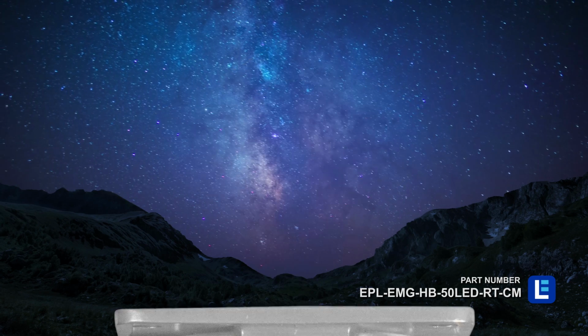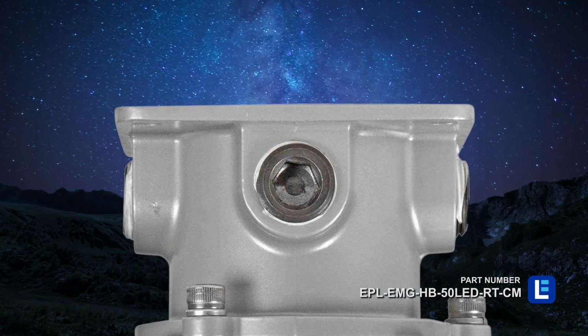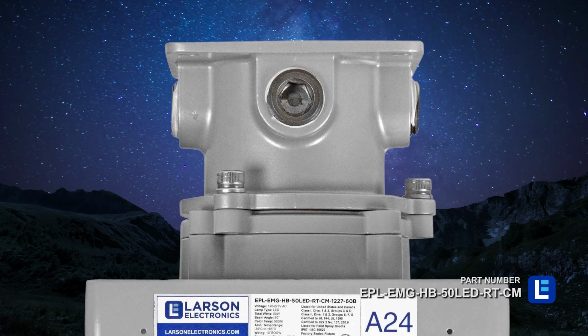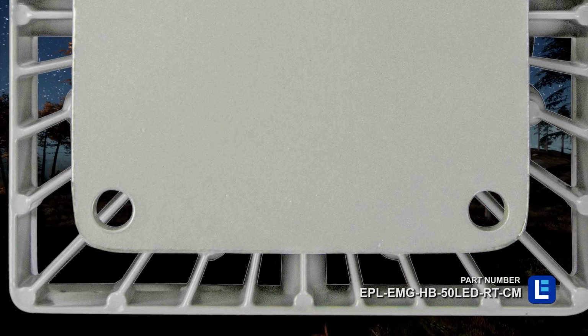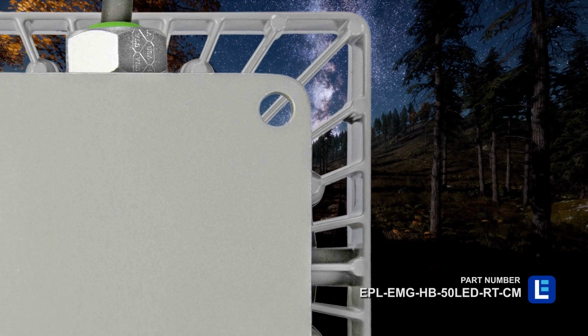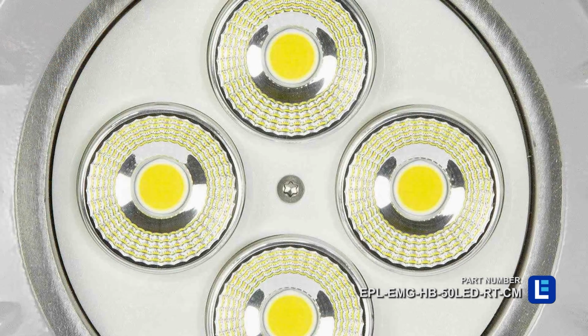This unit is equipped with a 4-bolt flat surface mounting system, which is suitable for ceiling, wall, and surface mounting applications. In emergency mode, the LED lamp will continue to operate at a lower light intensity level for 90 minutes via a remote battery. This Class 1 Division 1 and 2, Class 2 Division 1 and 2 explosion-proof light fixture provides 7,000 lumens of high-quality light while drawing only 50 watts.